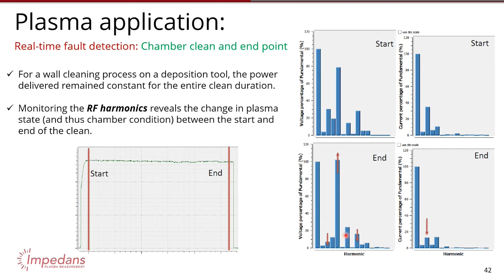There are also publications looking at low area endpoint detection. That's a challenge of the industry, monitoring below 5% or below 1% of the wafer being etched. Optically, that's really difficult now. But with RF, there are publications saying you get at least twice the sensitivity. From my own experience, on chambers where optical struggles to get below 2% of the wafer being monitored, we've demonstrated well below 1% or even below 0.1% of the wafer being etched.